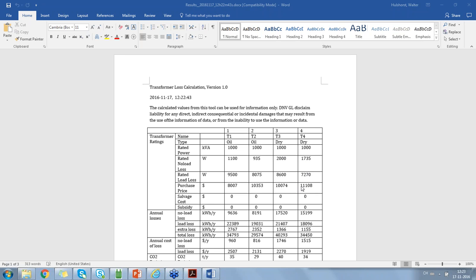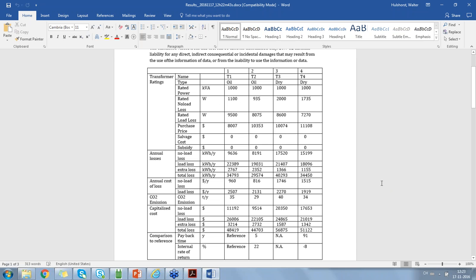You will see that transformer 4 is the highest value and transformer 1 has the lowest value. You can add all kinds of additional things you would like to do, like costing salvage cost if, with the transformer, you get some money back from subsidies or whatever. Based on the loading we have provided, the tool calculates the total amount of losses we have. In this case, it's showing the annual losses for the no load, for the load, and also for the extra losses we have, and then counts them all together.